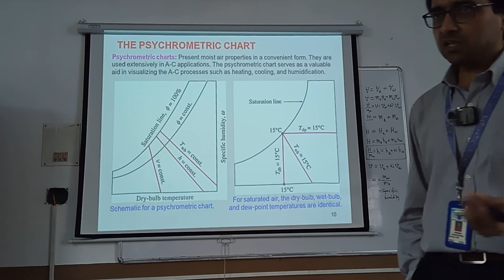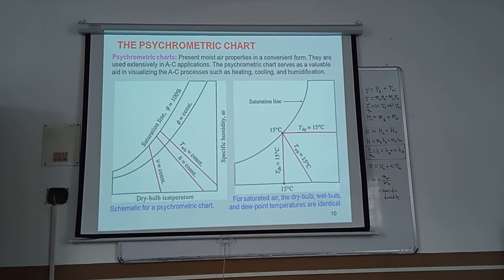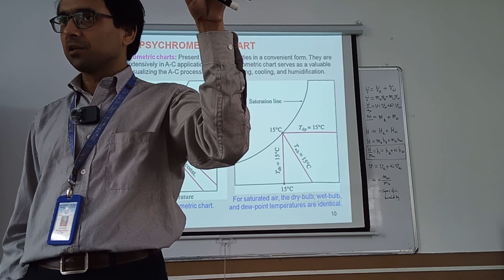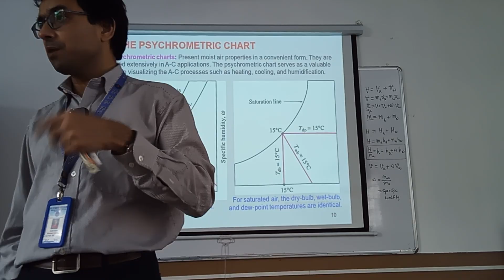humidity control. Controlling the temperature alone is not enough, you have to control the humidity also, because if the humidity is very low, then we will feel dry. There will be too much evaporation from the surface and we will feel dry. If the relative humidity is too high, then we will feel sweaty and the sweat will not evaporate easily, because sweat evaporation depends on the relative humidity. If I am sweating due to high temperature but cannot evaporate that sweat, I will not feel enough comfort. So relative humidity is also an important parameter.